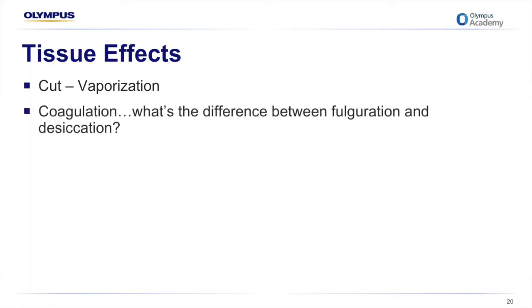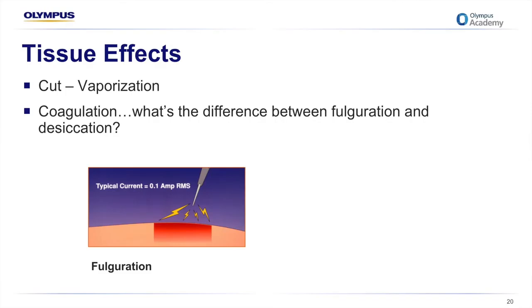So with regards to cut or vaporisation, that gives you little to no coagulation. And within coagulation, there's two different types. You can have a fulguration, which has high voltage and low current. The surgeon holds the electrode a short distance from the tissue and an arc jumps from the electrode to the tissue. There's no contact between the active electrode and the tissue. Its main purpose is to provide a broad, superficial and rapid coagulation. In this situation, the tissue is charred.